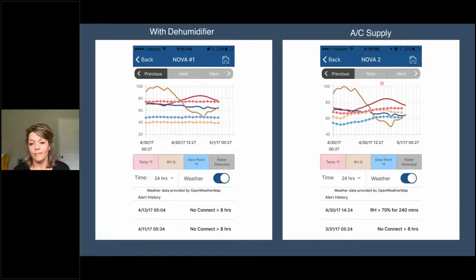Both were built as habitat, energy efficient, EarthCraft standard homes, and in both the occupants didn't run their air conditioning very low. When you put conditioned, colder dry air into a crawl space, it actually increases relative humidity. The one with the dehumidifier, left running on its own, stayed very controlled.